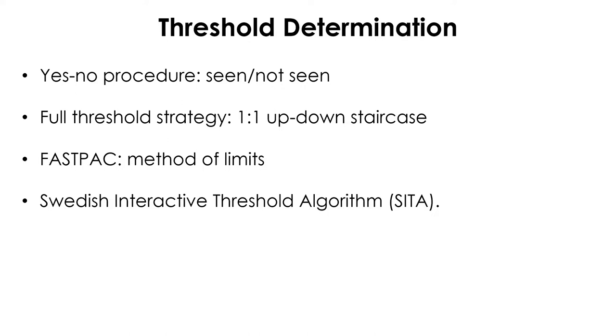Depending upon the number of test locations and the level of abnormality, the test can easily take more than 15 minutes, which can be quite time-consuming and demanding for clinical purposes. For that reason, faster algorithms have been developed to cut down testing time. FASTPAC is an early example of such effort, which uses a 3 decibel step size and estimates the threshold after only one reversal, except for four primary seed locations in which standard full-threshold testing is carried out.